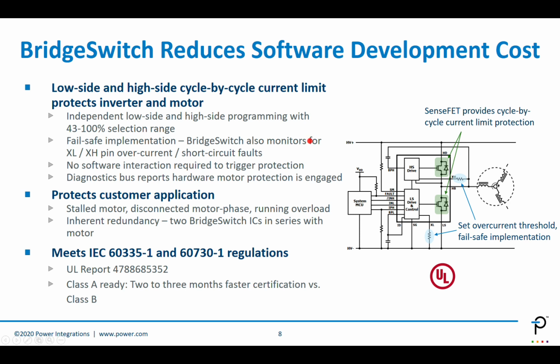BridgeSwitch also monitors for short circuit or overcurrent faults. There is no software interaction required to trigger the protection. This is an intrinsic built-in hardware protection which works cycle by cycle. When the current limit has been reached or has been exceeded, the FET switches off.